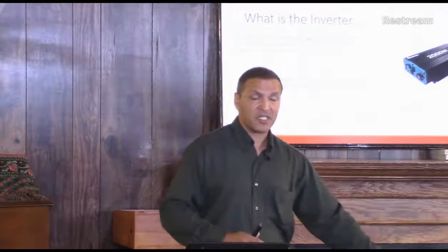Lead acid batteries are 500 to 700 cycles, meaning drain, charge, drain, charge. A lithium iron phosphate can get you anywhere from 5 to 10,000 cycles. People say, well, they're expensive. 5 years ago, maybe 3 years ago, I'd say yes, but now it's a 1.5 to 1 ratio, so the price is coming down to where lithium iron phosphate is very affordable.